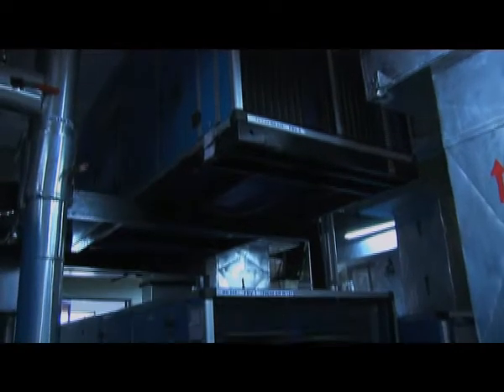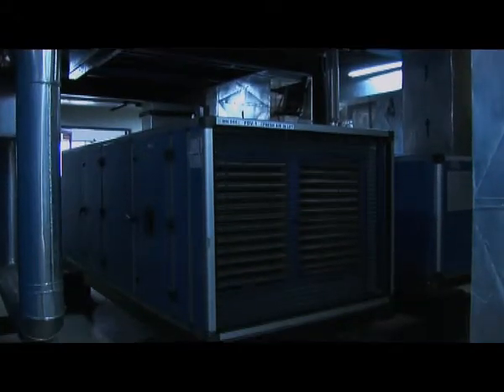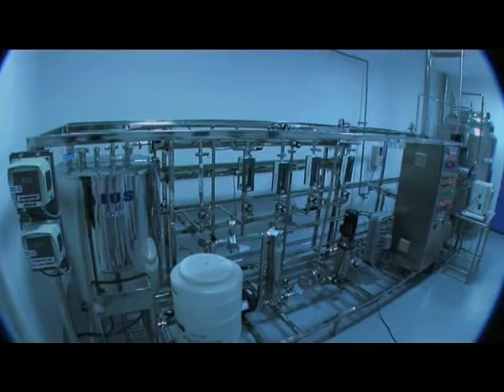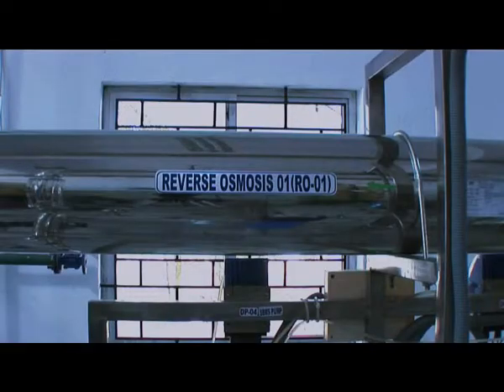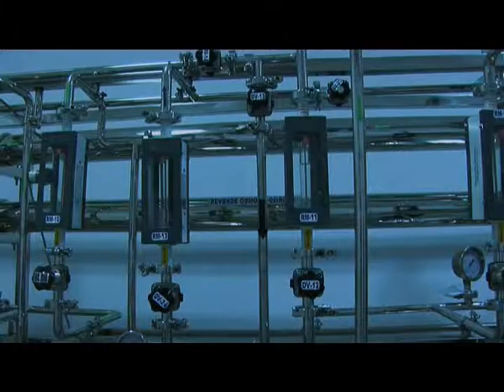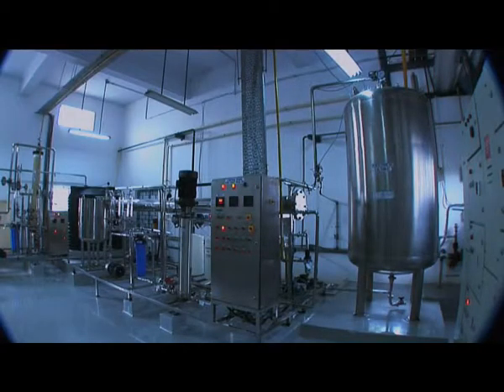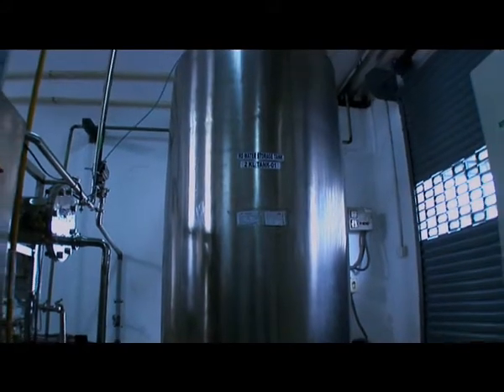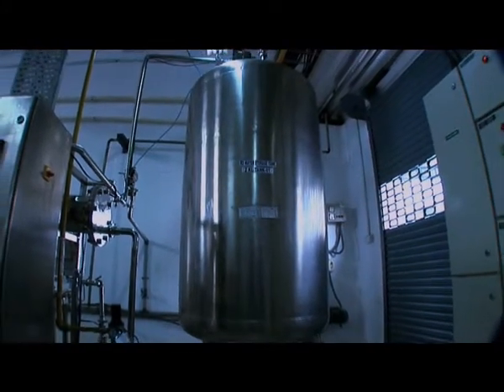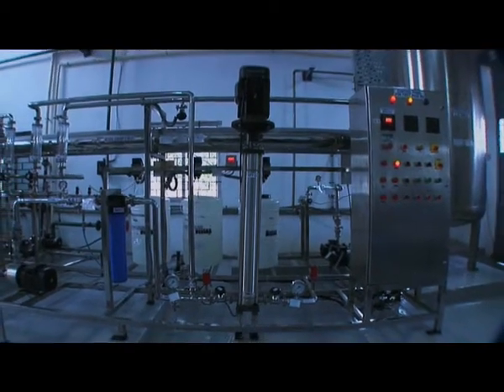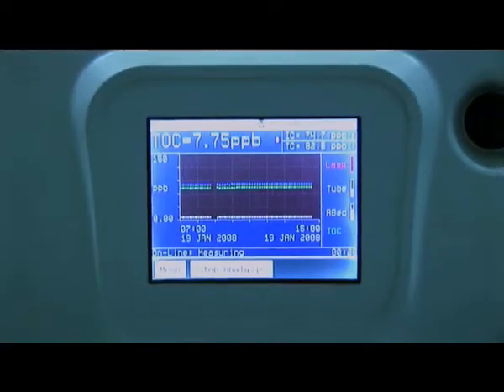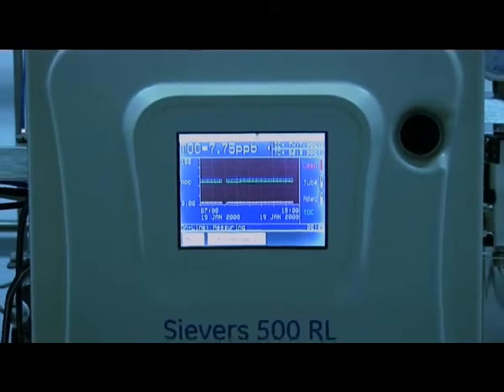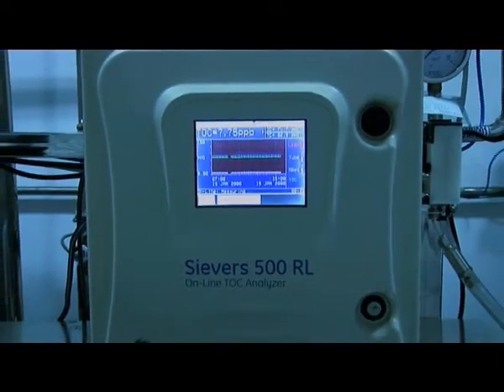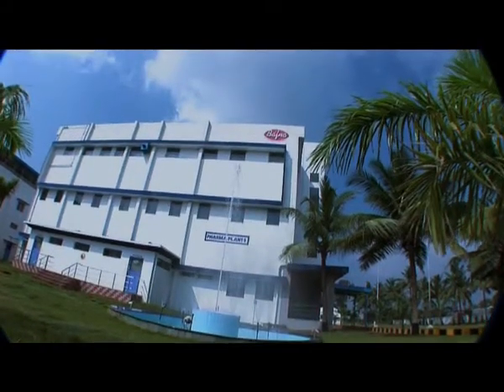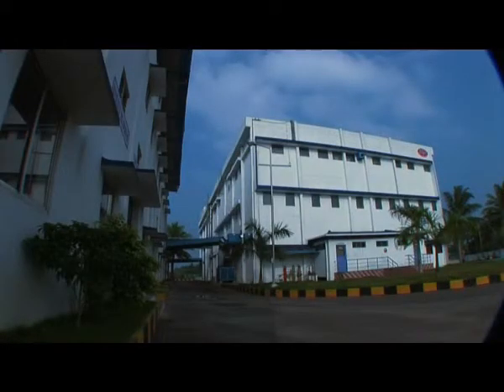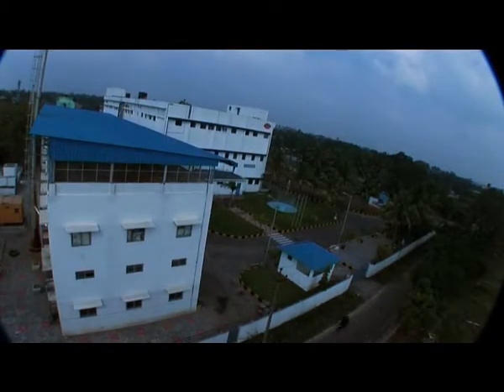With top ISO qualifications, the plant is operational with 7 AHUs. The ultra-modern water circulatory system with a double reverse osmosis facility and an electrodeionizer provides water of USP quality. The storage of purified water is ambient and recirculatory at a flow rate of 1.2 meters per second round the clock, monitored continuously for its conductivity and online total organic carbon. Bafna Pharmaceuticals is also one of the few pharmaceutical companies to have its own nitrogen gas storage facility in the warehouse.